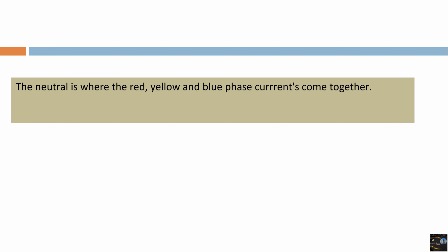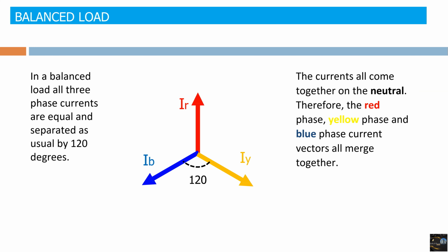So in short, the neutral is a point where all the other three phase currents, that is red, yellow and blue, come together. To study in detail, let's see the two conditions. The first one is the balanced load. As you can see, in a balanced load, all the three phase currents are equal and separated by 120 degrees. So the whole clock will be 360 degrees and the angle between one phase and another phase is 120 degrees. The magnitude depends on the load.